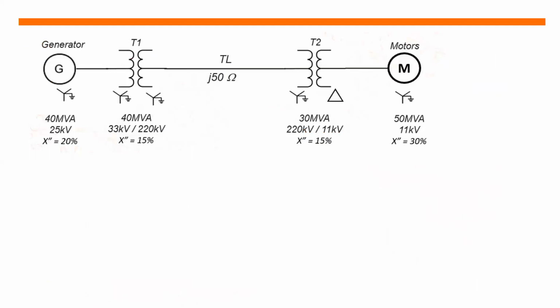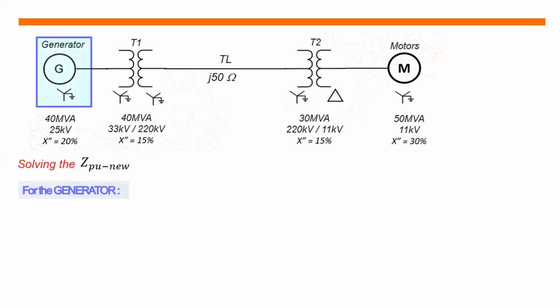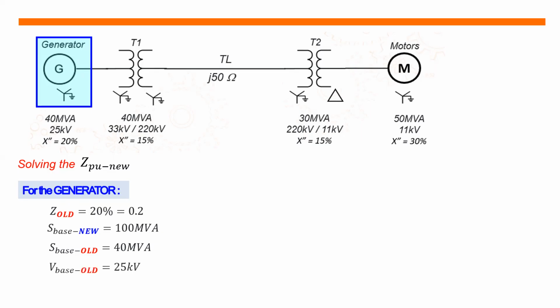So, ang step number 1 natin, so-solve natin lahat ng ating component, yung kanilang per unit values. So we will start with the generator. So solving for the new per unit impedance of the generator, so let us write all the given value first. The old per unit impedance is equals to 20%, and the new base power is equals to 100 MVA. The old base power is equals to 40 MVA, as stated in the nameplate of the generator. The old base voltage is equals to 25 kV, and the new base voltage is equals to 33 kV. Dahil papasok siya doon sa, as ang output niya is 33 kV, which is papunta doon sa primary side ng ating transformer.